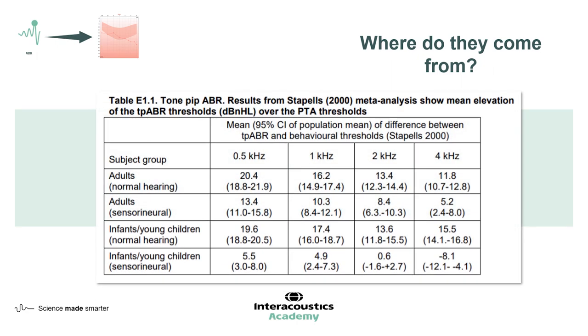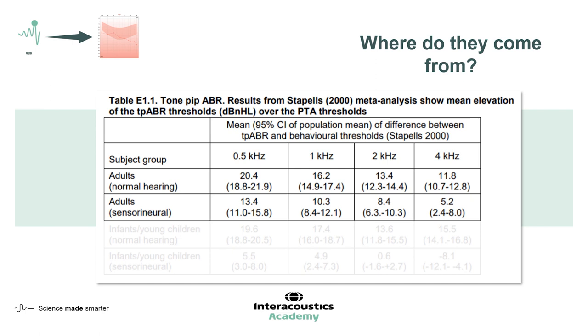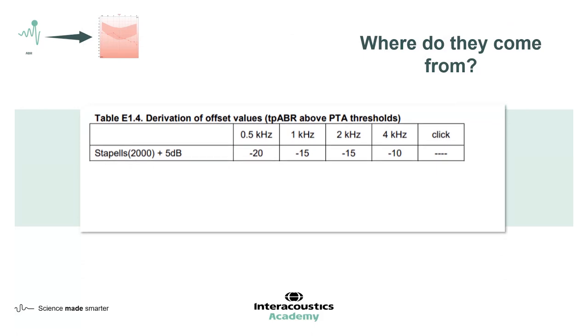The BSA correction factors were derived from this data with the following assumptions. They used adult data in preference to paediatric data from this analysis, as the measure of the behavioural threshold — being pure tone audiogram in adults — was likely to be more consistent across the individual studies. No correction was applied for the difference between the ABR threshold in adults and babies, because it wasn't possible to find sufficiently consistent data in the literature. The BSA paper uses a definition of threshold as the lowest clear response. An estimated correction of 5 dB has been applied on the basis that much of the published data were likely gathered under ideal test conditions, and threshold in some studies is likely to have been defined with a less strict criterion than the lowest clear response.